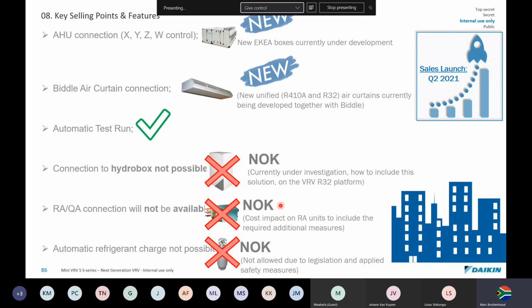The reason that we do offer that connection, and you need this little box, is that if you select a Sky Air unit or a fancy looking one, or one of the curved Amuras, this box is where the expansion valves are. If this was a normal split unit and you like the look of the indoor unit, there are no expansion valves on the indoor unit. The expansion valves are on the condenser. So Daikin have had to build this box, which you put as close as possible to the split unit, and then you can use it.